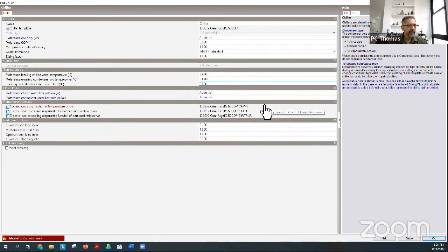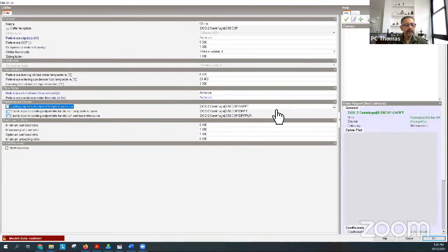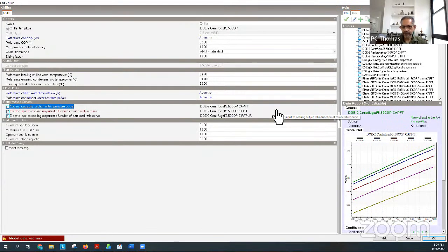You can view that. Again, if you don't have much detailed data on the chillers, this is not a bad chiller to use. But if you have some specific chiller that is really highly efficient, you may need to read through the literature and figure out how to provide a new set of curves for the chiller operation.